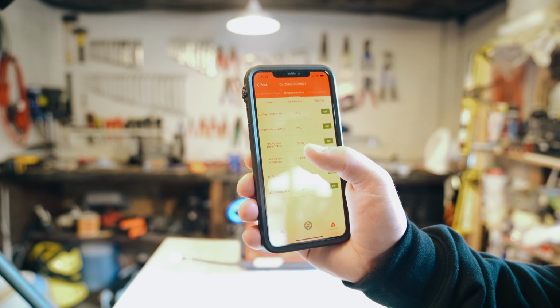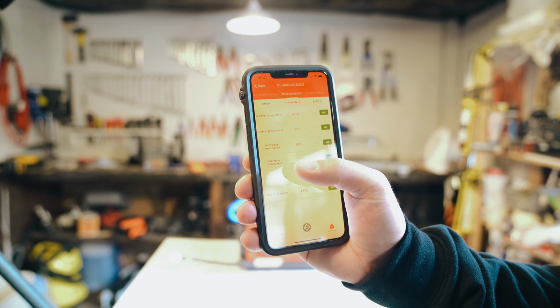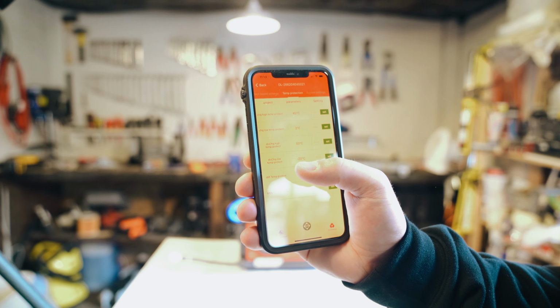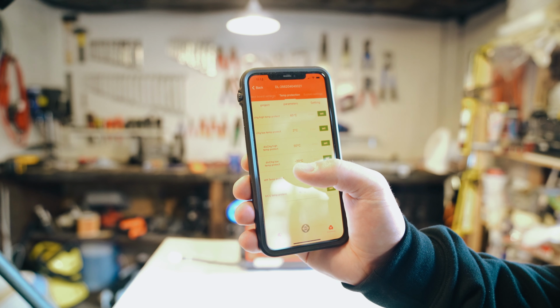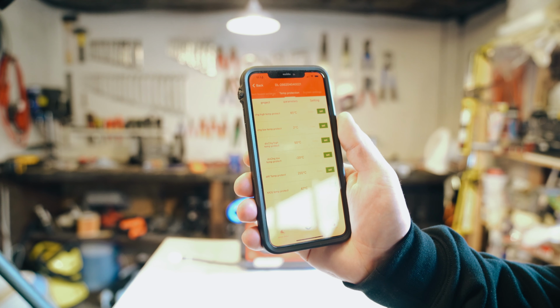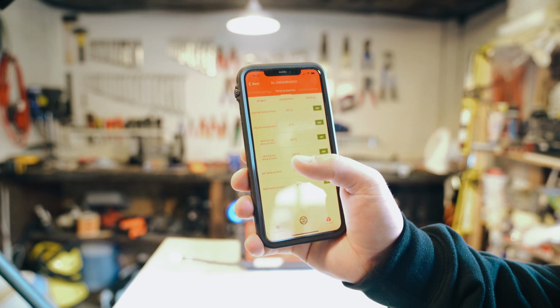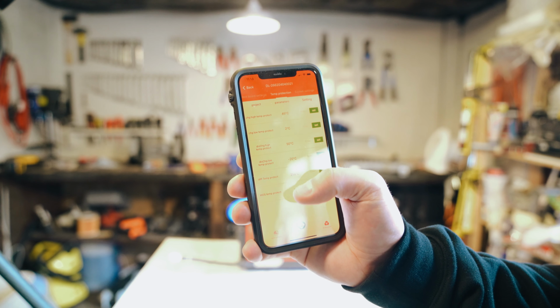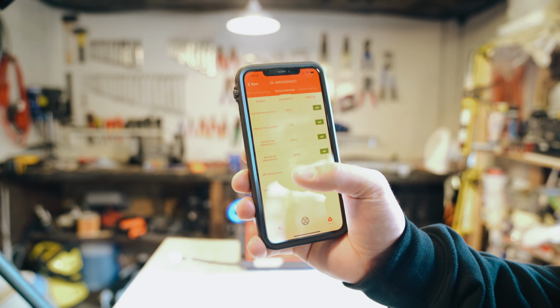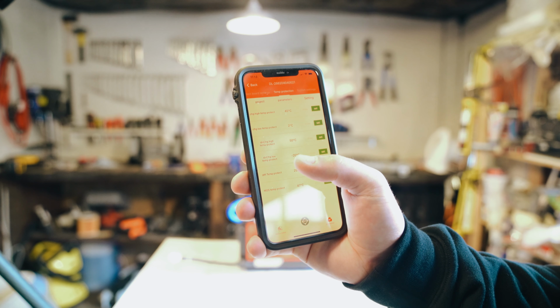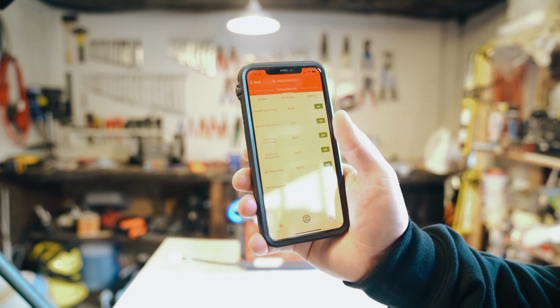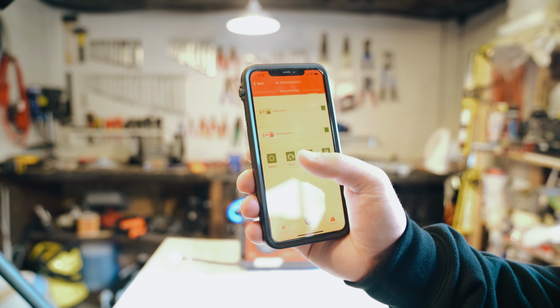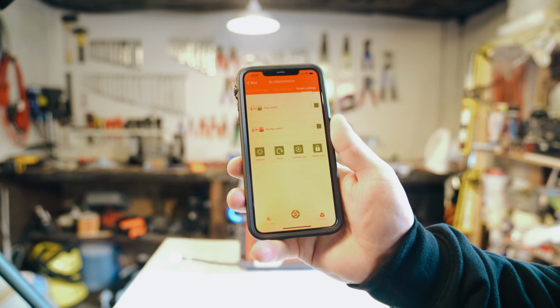Discharge high temp protect, I set as 50 degrees - again, I'm pretty much not going to be in a situation over that while drawing from the battery. Discharge low temp protect, minus 20 degrees - it's highly unlikely I'd be in that sort of temperature with this rig and battery, so that's what I'd set it to. If you live somewhere like Colorado, or somewhere that really gets cold temperatures, you'd have to adjust these and really look up the manual as to what they mean and what the BMS will do. And then this stuff I just leave on, these are just the controls for turning it back on and so on.